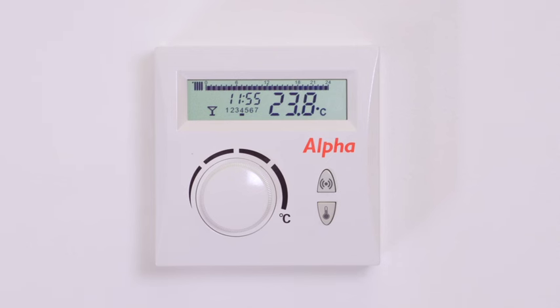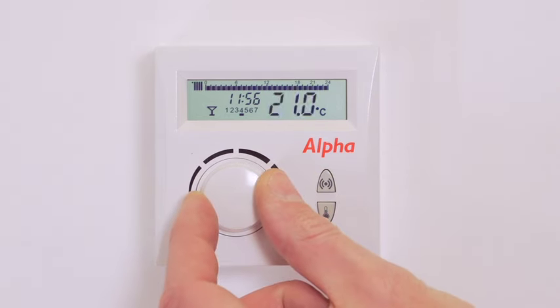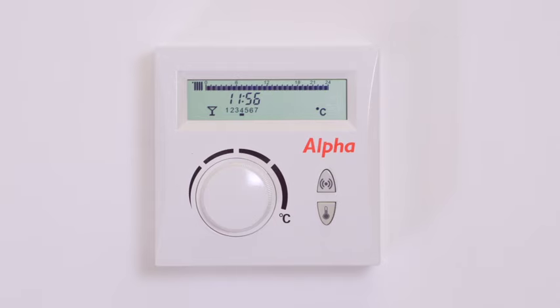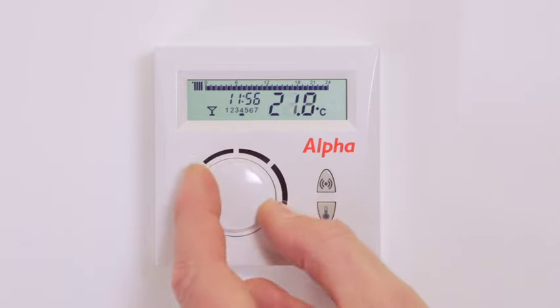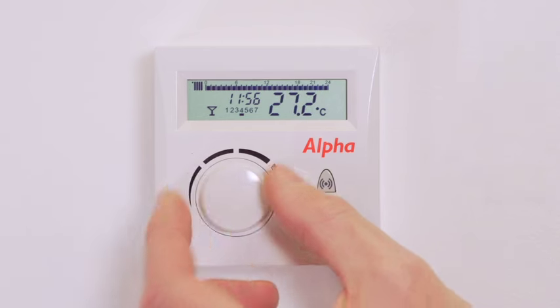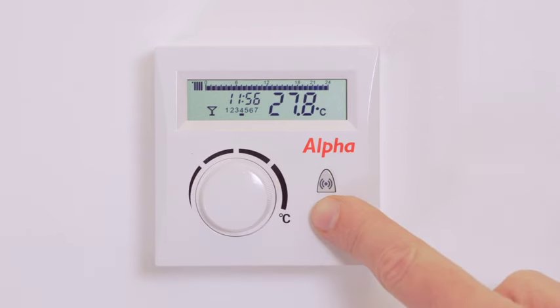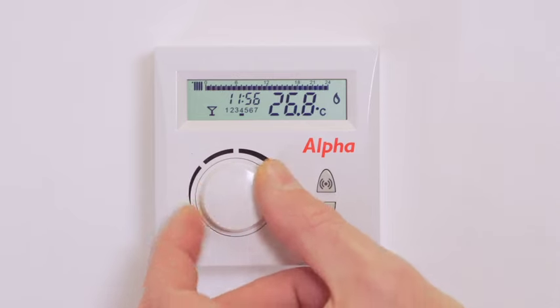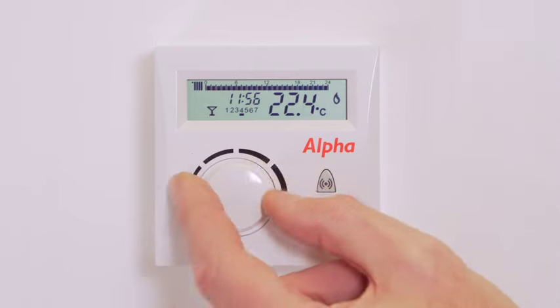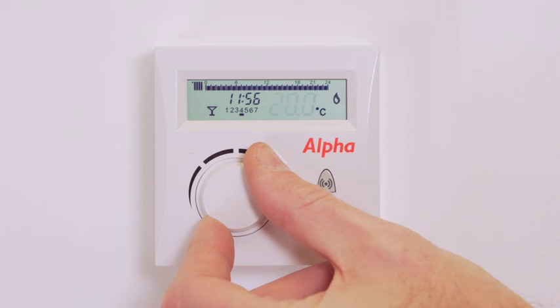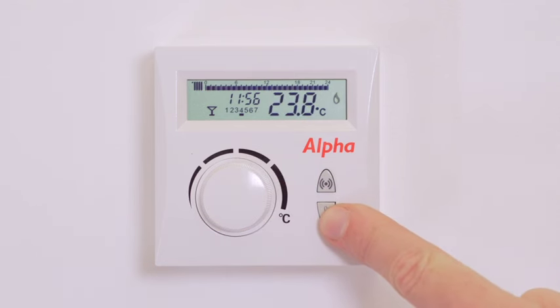Current room temperature is 23.8 degrees, and the thermostat is satisfied because the set point is only 21. If you want the boiler to come on, simply raise your set point above the room temperature, press the thermometer button, and you can see a flame symbol appears and the boiler will come on. And if you want to turn it down, turn the boiler off, drop the temperature below the current room temperature, press the thermometer button again, the flame symbol will go.